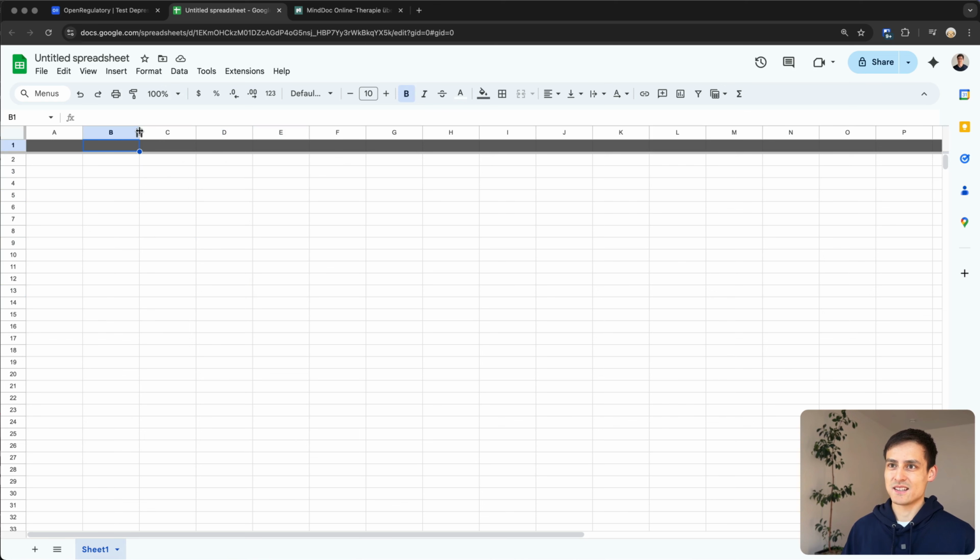So you have a column here, let's call it "what could go wrong." And then you could say, okay, you're treating people with depression, so maybe you could have a worsening of depression. And why might that be the case? Maybe because you have crappy content in your app. Maybe your app has medical content which is not very good, and it gives advice to those patients to do certain things, and maybe that leads to worsening of their depression. Wrong medical content in app, and then you have worsening of depression.